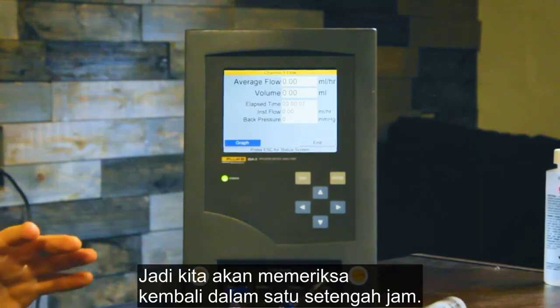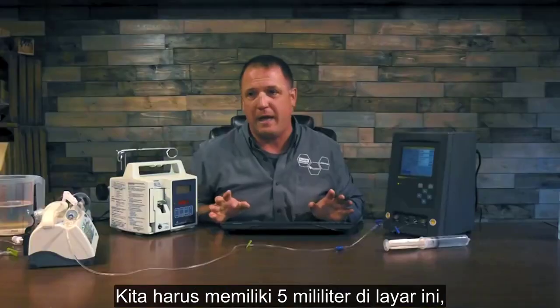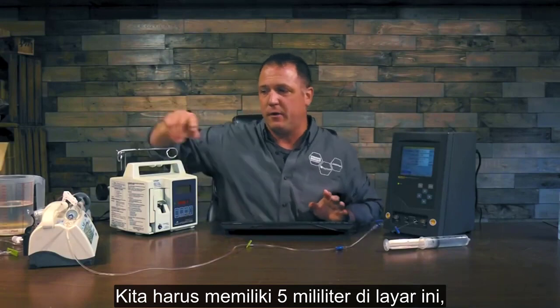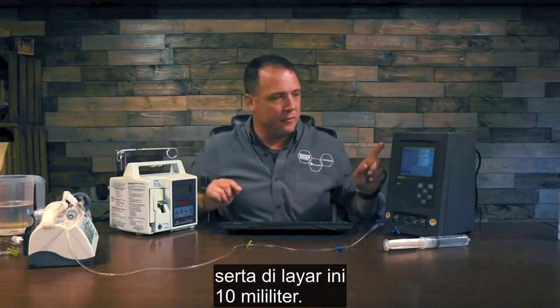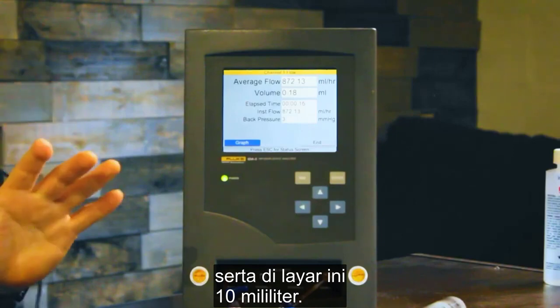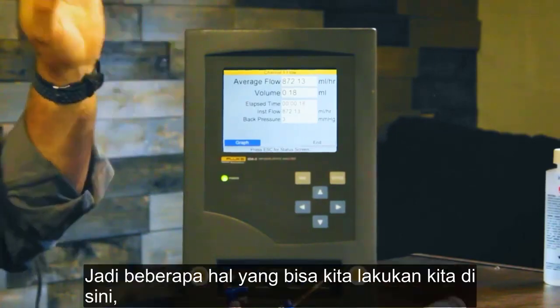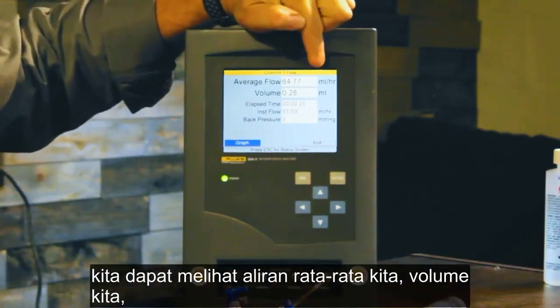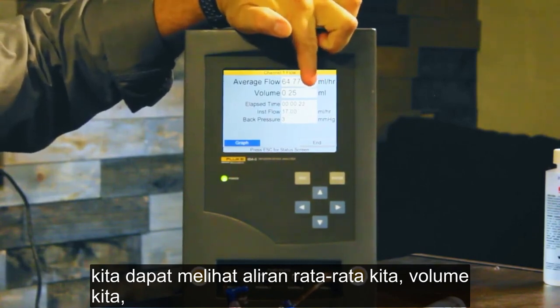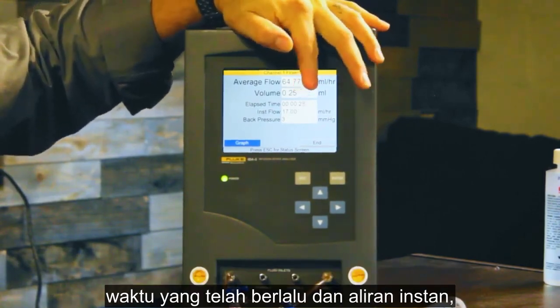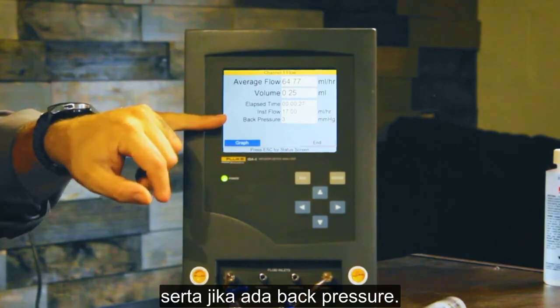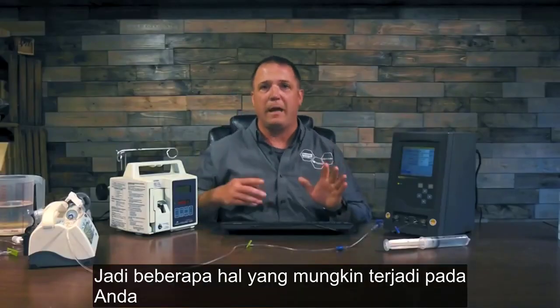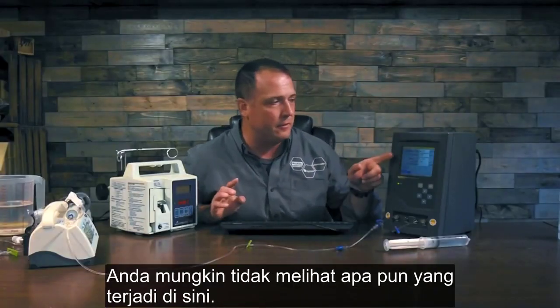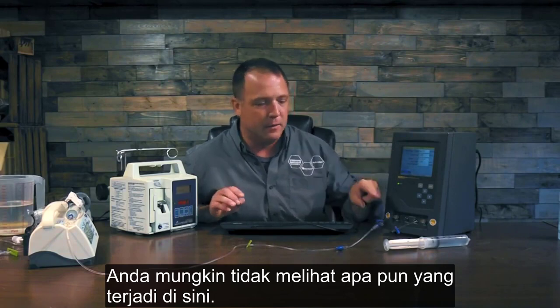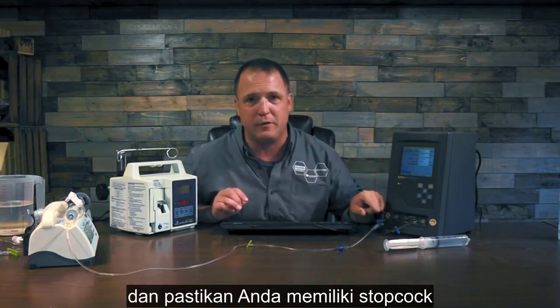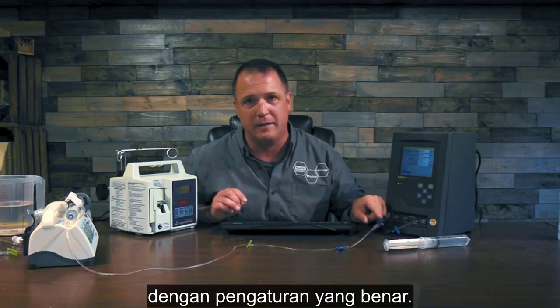So we're going to check back in half an hour. We should have 5 milliliters on this screen, as well as on this screen, and 10 milliliters. So I know this has started, so some things we can do while we're here. We can see our average flow, our volume, our elapsed time, and our instant flow, as well as if there's any back pressure. So some things that might happen to you when you're running these tests. You might not see anything happening here. Double check your stopcock and make sure that you have your stopcock turned in the correct setting.